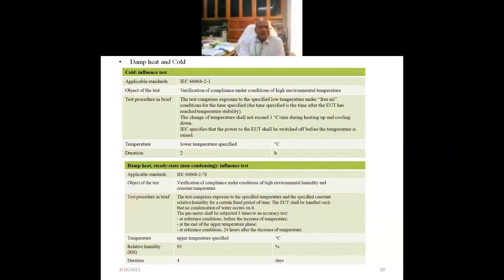Damp heat, steady-state, non-condensing influence test, and the applicable standard is IEC 60068-2-78. Object of the test: verification of compliance under conditions of high environmental humidity and constant temperature. Test procedure in brief: the test comprises exposure to the specified temperature and the specified constant relative humidity for a certain fixed period of time. The EUT shall be handled such that no condensation of water occurs on it.